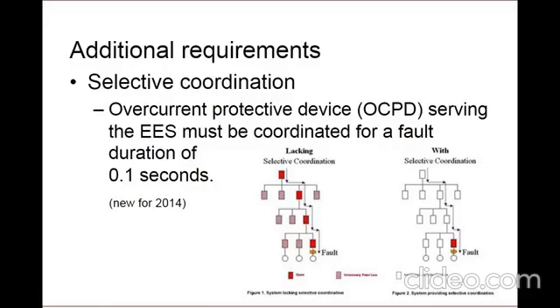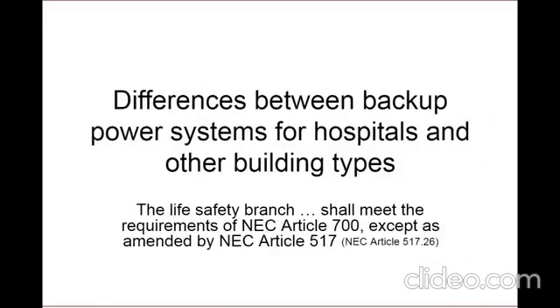Now, something that was added in the 2014 version of NFPA 70, Chapter 517, now limits selective coordination requirements to a fault duration of 0.1 seconds and beyond. This differs from the requirements of Article 700, which requires full selective coordination, typically interpreted to mean 0.01 seconds and beyond. NFPA 99 relaxed this requirement in the 2012 version, and now the NEC got caught up with it in 2014. This is real good news for the healthcare world because it allows the engineer to really consider other factors, such as arc flash hazards, equipment damage, risk of fires, or extended outage concerns, which are harder to accommodate when designing to meet Article 700. So now back over to you, Rob.